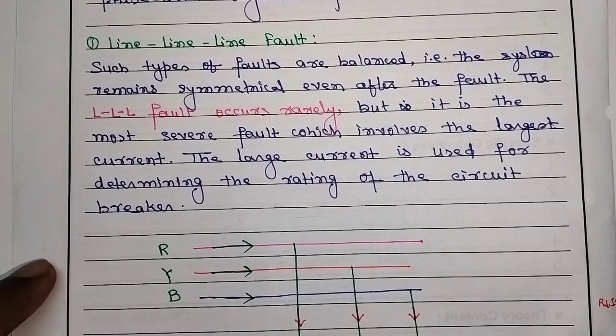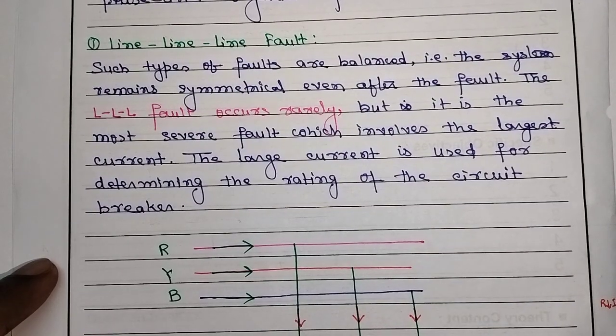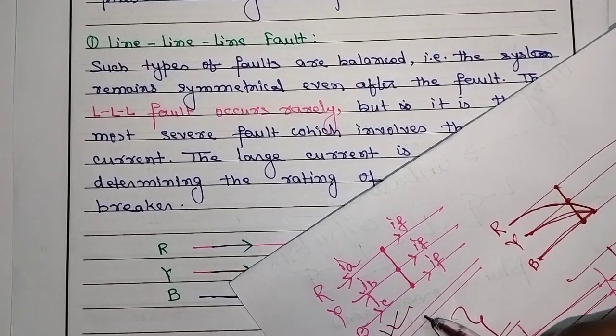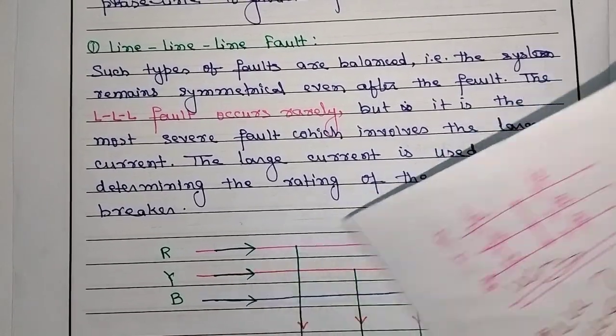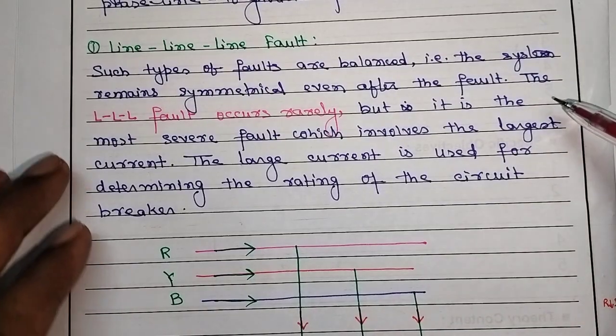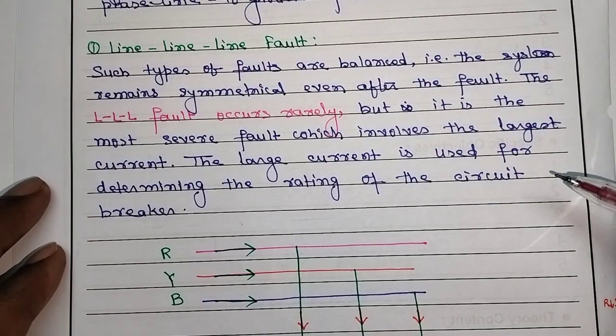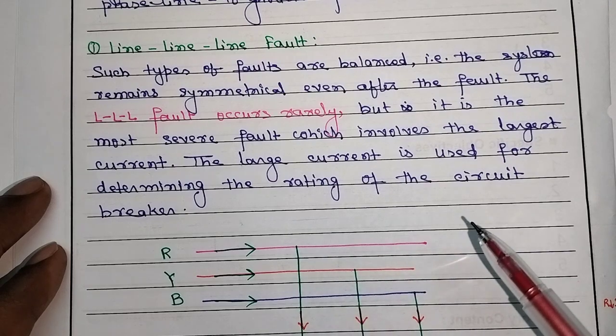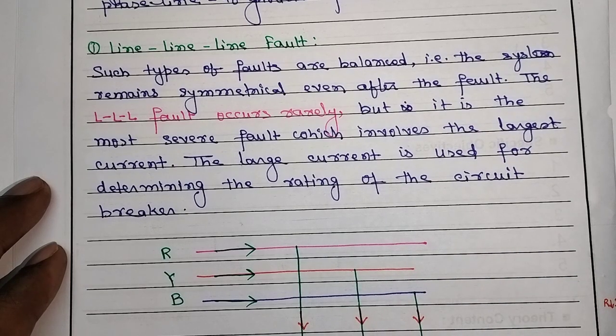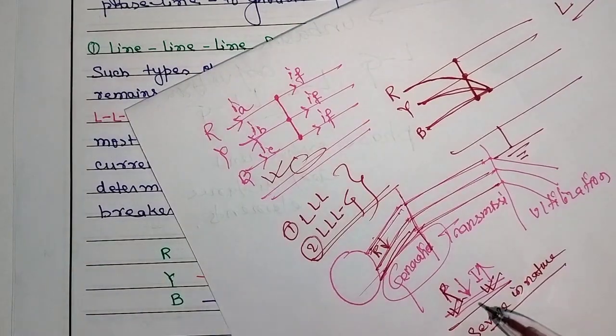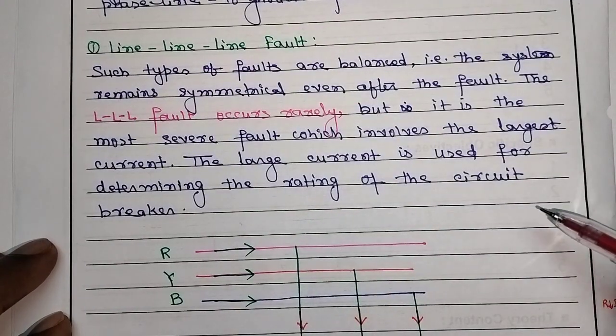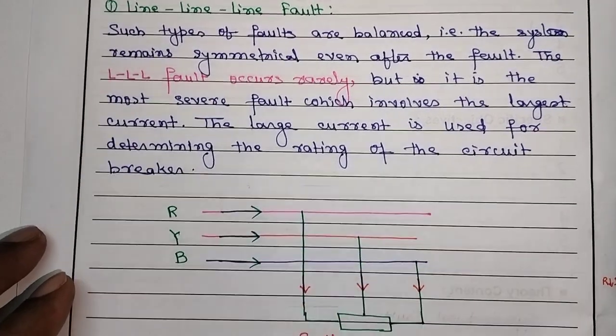Already I have told you that whenever a fault occurs in the system, the system remains balanced, it is not going to change. The LLL fault occurs rarely, but it is the most severe fault, which involves the largest current. This large current is used for determining the rating of the circuit breaker.